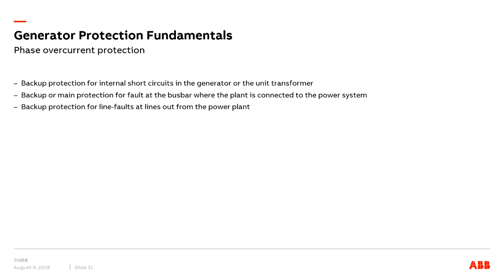And then we have the phase over current protection, which again has two different tasks. The primary one is to detect and clear internal faults in case of a main protection failure, which is the differential protection. And the second one is to detect and clear external faults, mainly in case of a main bus bar or line protection failure.